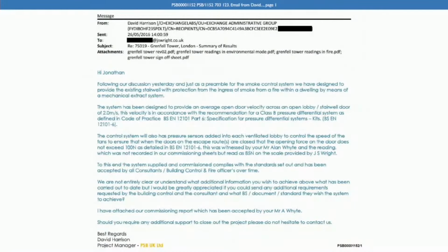Now, can we agree that the way that email is written suggests that in fact it was only one opening door force measurement which was recorded? He says this was witnessed by your Mr. Alan White, and the reading, which was not recorded in our commissioning sheets, but read as 85 newtons on the scale provided by J.S. Wright. Do you agree that that email suggests that, in fact, only one reading was taken at 85 newtons? Yeah, but as I've said, we did it on every floor. So I think what you're saying is that's not consistent with what you remember doing, which was actually to test on every floor, yes? We definitely tested every door, every floor. We started at the top and worked our way down.